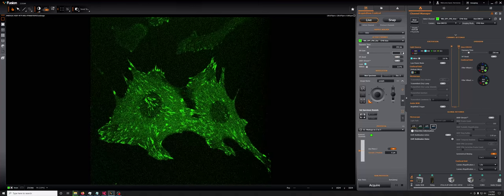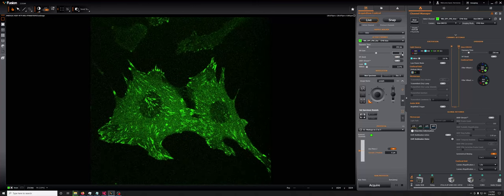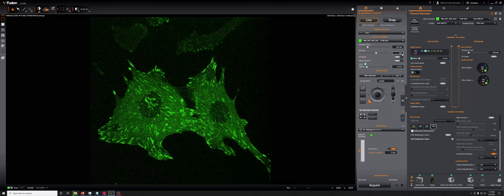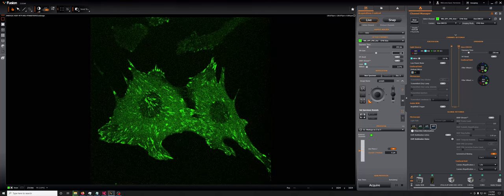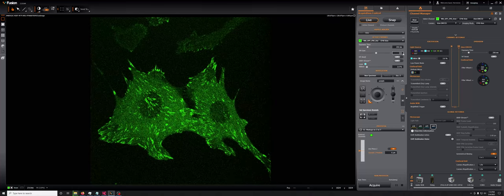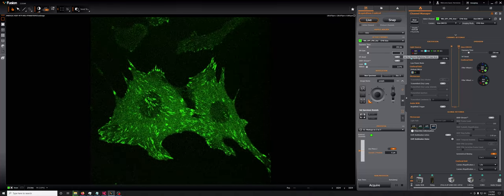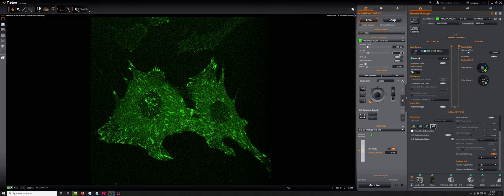But if we go from 80 to 160, we no longer see that much of an improvement. So there's no point in increasing the EM gain beyond 80.